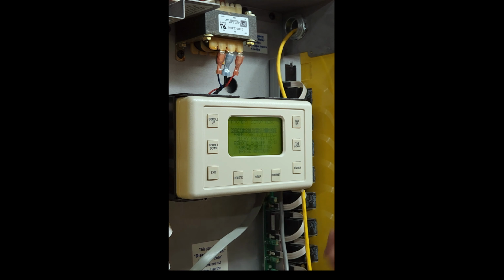Okay, hit enter on addressing bus scan. Then you see auto addressing is first on. Hit enter. Hit the button called scroll up until it says start address 46. Now we're going to address that switch to number 46. Okay, 46. There are two ways you can address this. Don't touch anything on the screen. The switch either has a black button on the back or the one button in the front. You press only one of them.